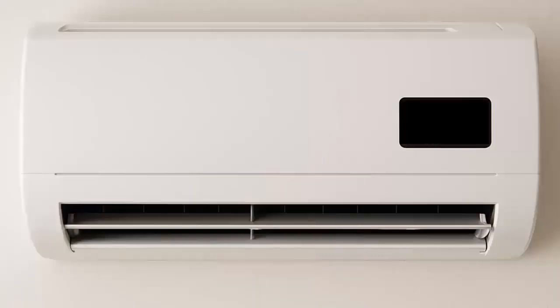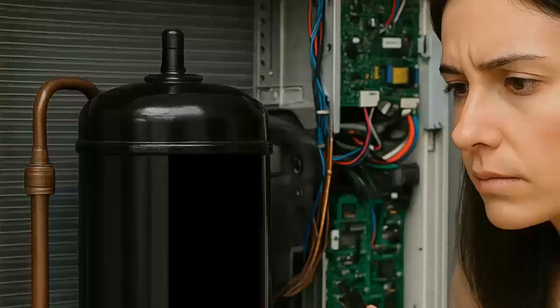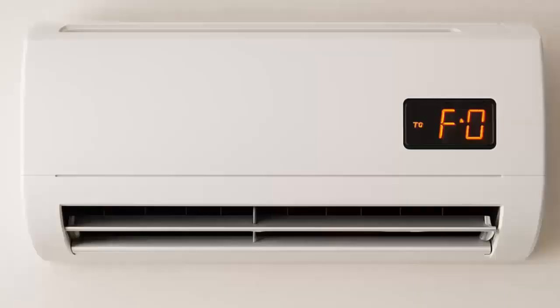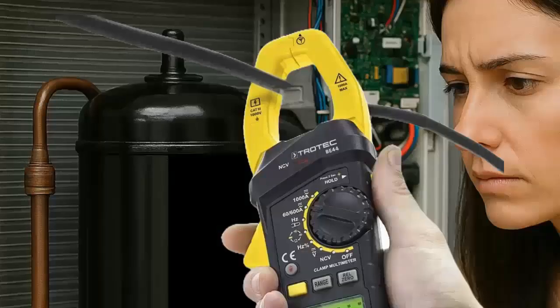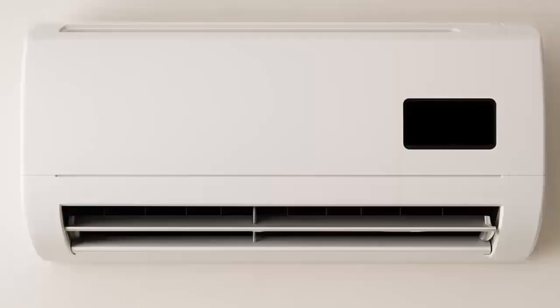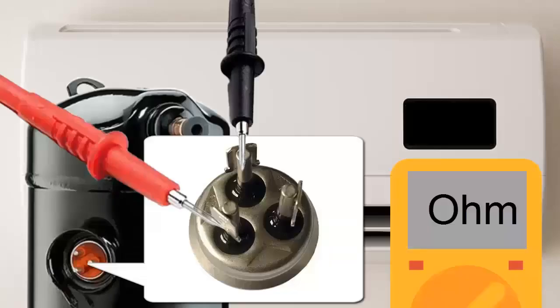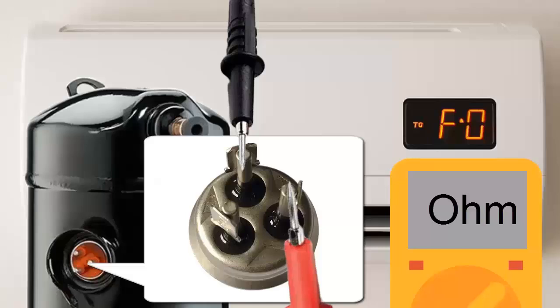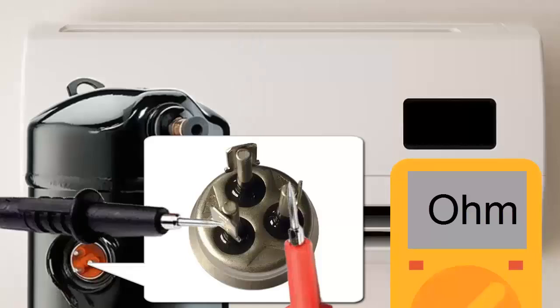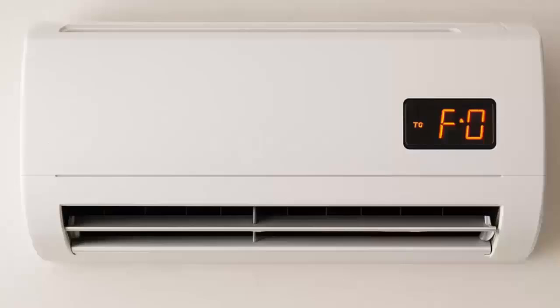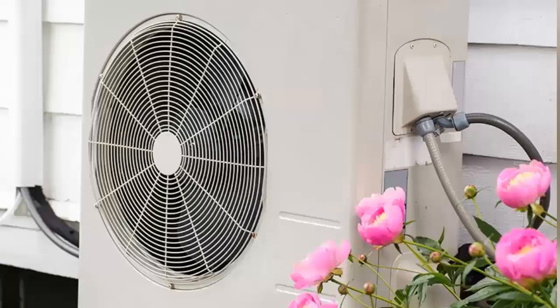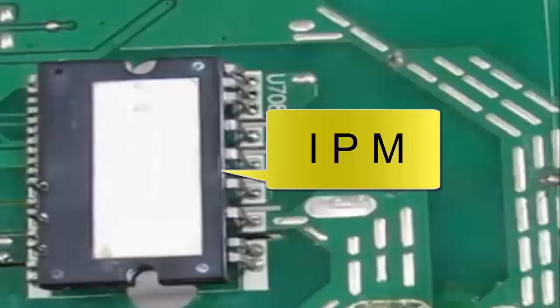Steps to follow. A. Check the wiring connections feeding the compressor. B. If the compressor starts, measure its current draw and compare it with the value on the label. C. If it's an inverter unit, measure the resistance between the compressor pins. The values should be similar. D. If the code appears after some time running, the issue might be a fan or a dirty coil. E. If no problem is found in an inverter unit, suspect the IPM, Intelligent Power Module.